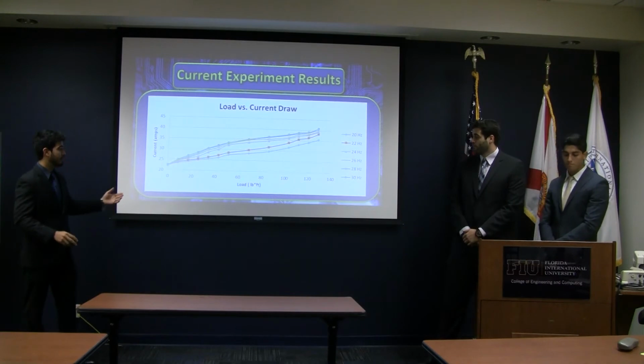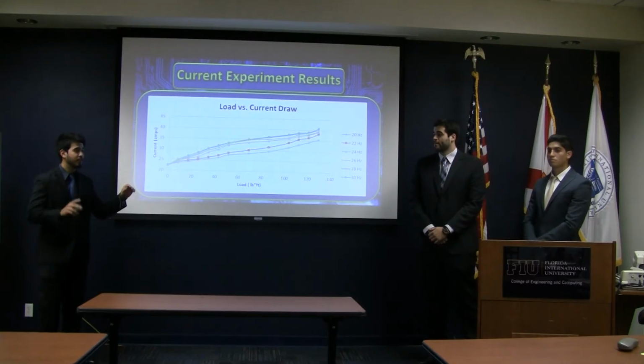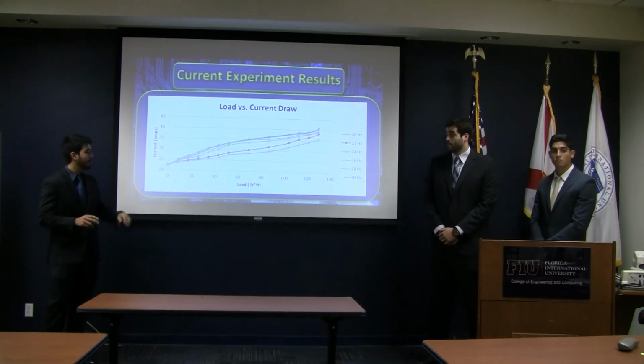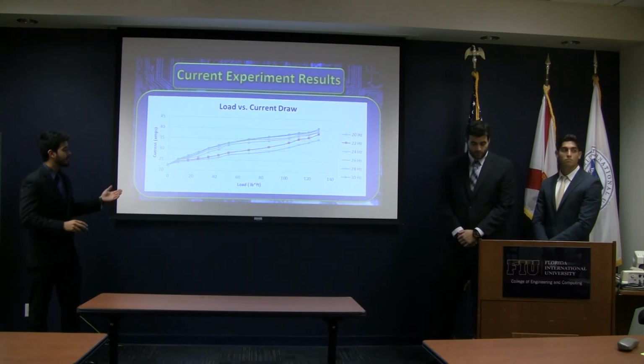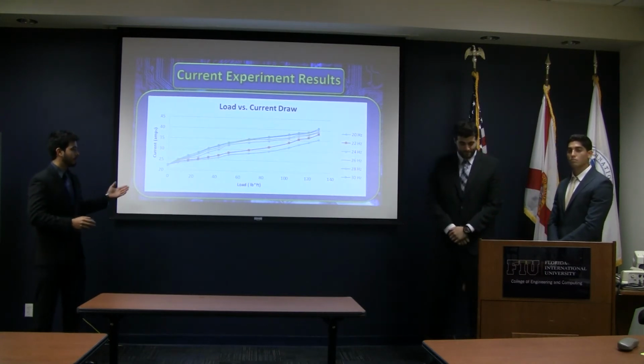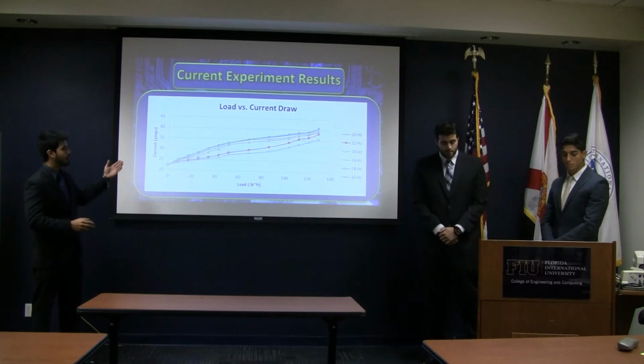So ultimately, this is what we ended up finding. We changed the driver settings from 20 hertz to 30 hertz. That way we could see, as we expected, that as load is increased, our system was able to catch an increase in current draw.